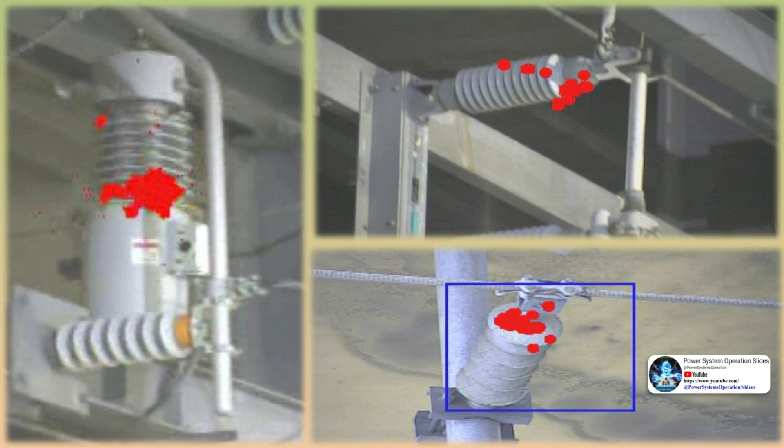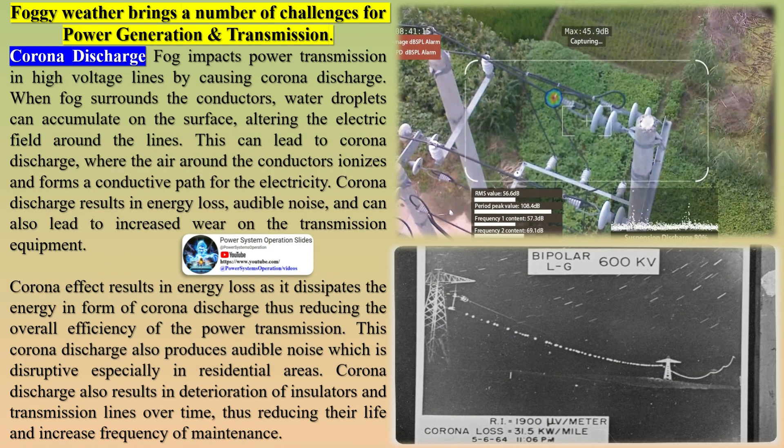Energy dissipation: the ionized air particles collide with neutral air molecules, transferring some of their kinetic energy to the neutral molecules. This transfer of energy results in the dissipation of power, known as corona loss or corona discharge loss. Factors affecting corona losses include conductor size and surface condition — smaller conductors or conductors with irregular surfaces tend to have higher electric field gradients, leading to increased corona losses. Higher transmission voltages generally result in higher corona losses, as electric field strength is proportional to voltage. Weather conditions such as humidity, air pressure, and precipitation can also affect the ionization of the air and the magnitude of corona losses.